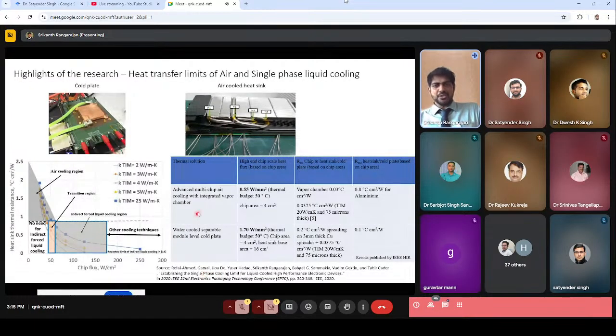As you can see from the table, advanced air cooling with integrated heat spreading elements like vapor chambers and heat pipes can remove heat up to 55 watts per centimeter square for a thermal budget of 50 degrees Celsius. Thermal budget here means the temperature difference between the chip and the cooling fluid, so in a 50 degree C thermal budget, we remove 55 watts per centimeter square.